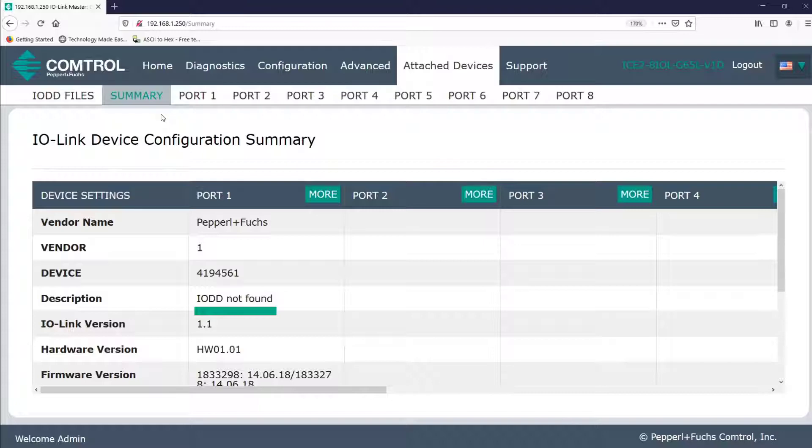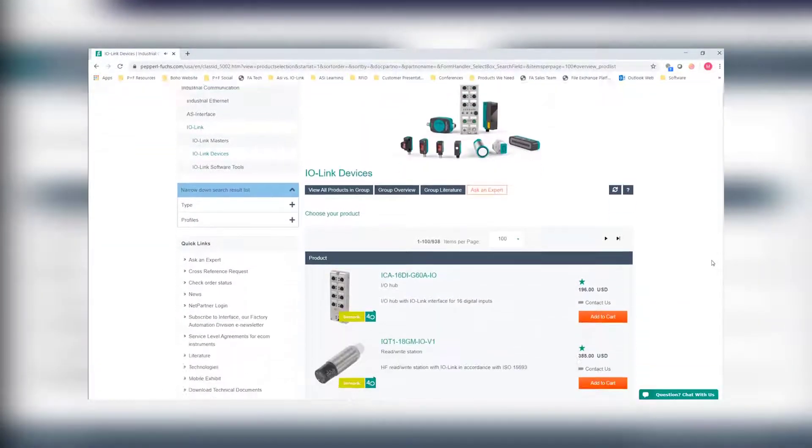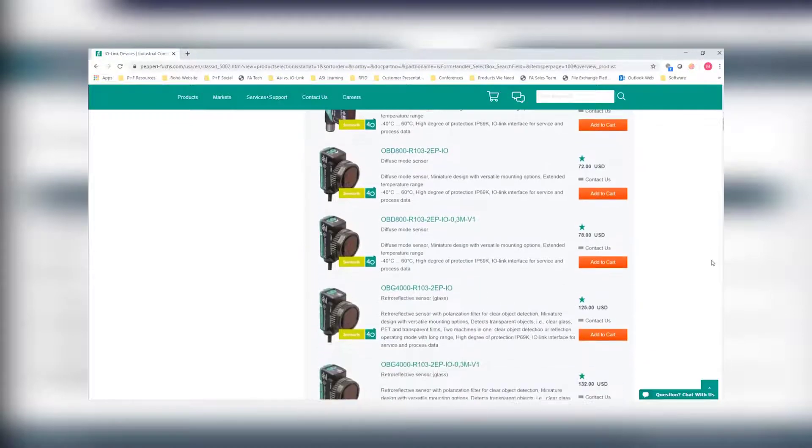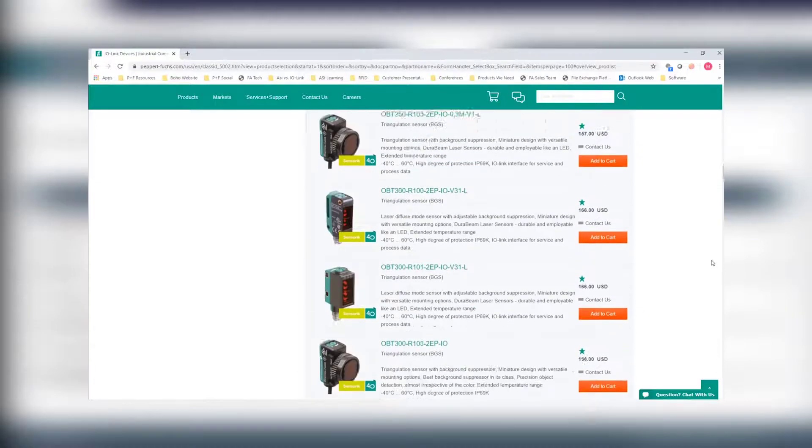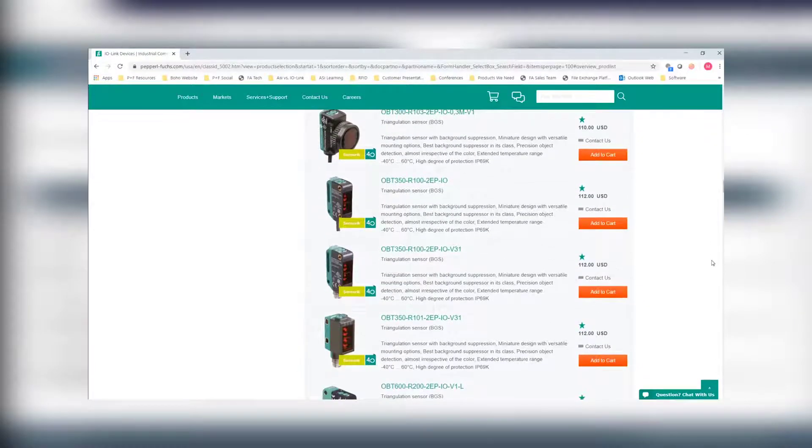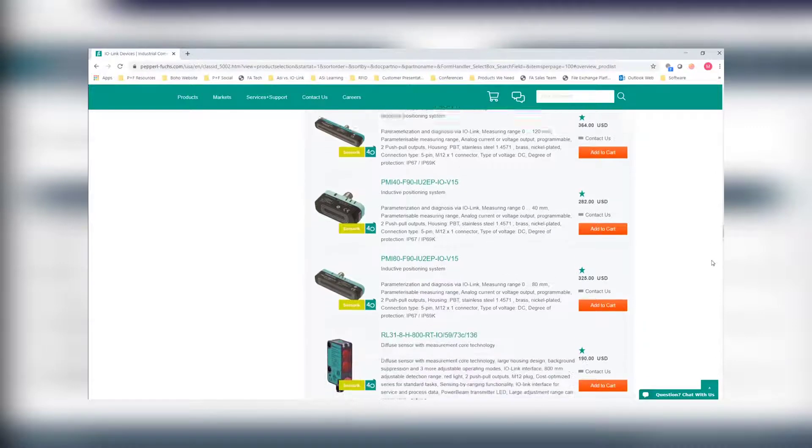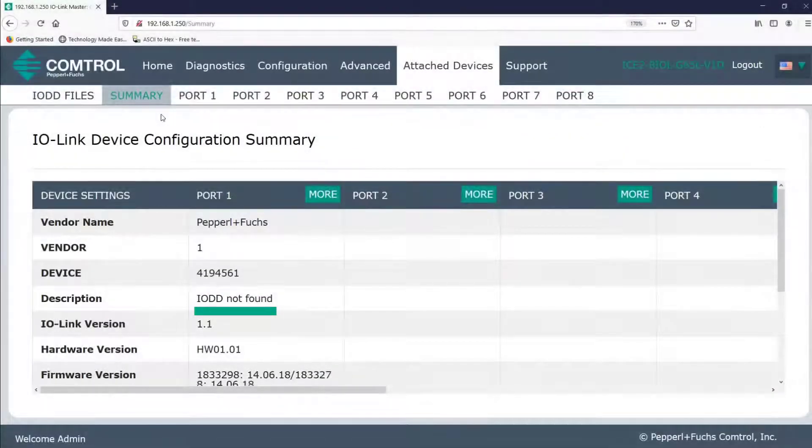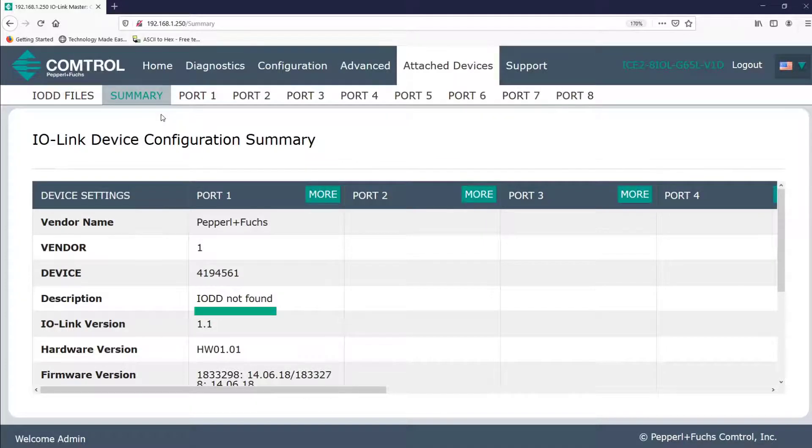So briefly, let's talk a little bit more about the IO-DD file. The IO-DD file is needed because IO-Link devices are different from one another, and there are a lot of them. It would be hard to continuously update IO-Link masters with correct and up-to-date information for all the IO-Link devices that currently exist and will exist in the future. And that's what we have an IO-DD file for. It tells the IO-Link master all about the device that we're connecting to the IO-Link master, and it allows us to easily view settings that can be changed right through the web interface.